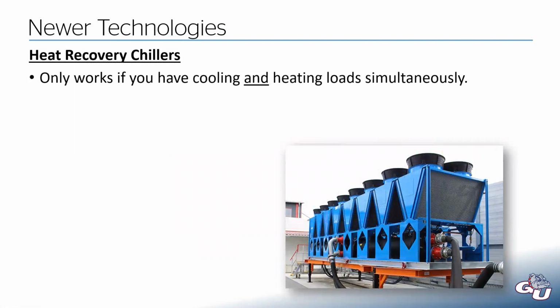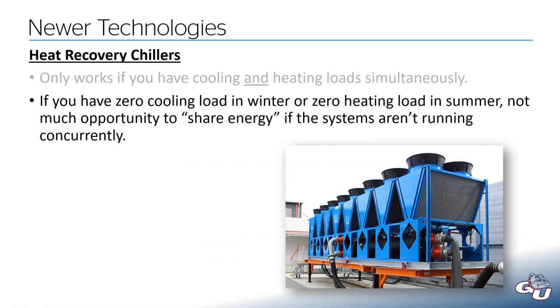Now, this only works if you have heating and cooling loads simultaneously. If you have no cooling load in the winter or no heating load in the summer, where's the opportunity to share energy? If those two systems aren't running at the same time, then what's the purpose in sharing this energy around? And that is true with most commercial buildings. If you look at a typical school or a typical office building, this is true.